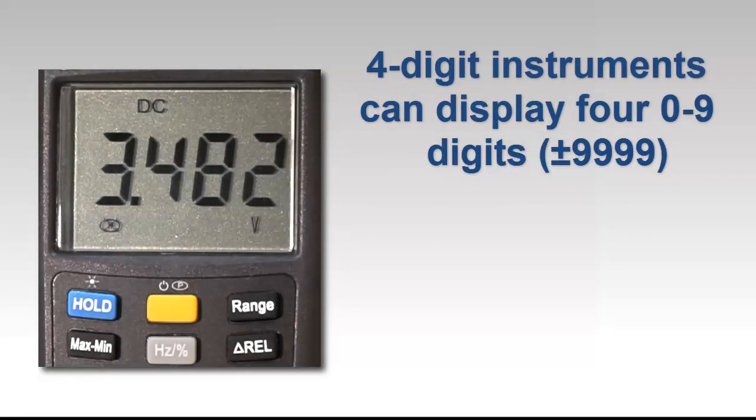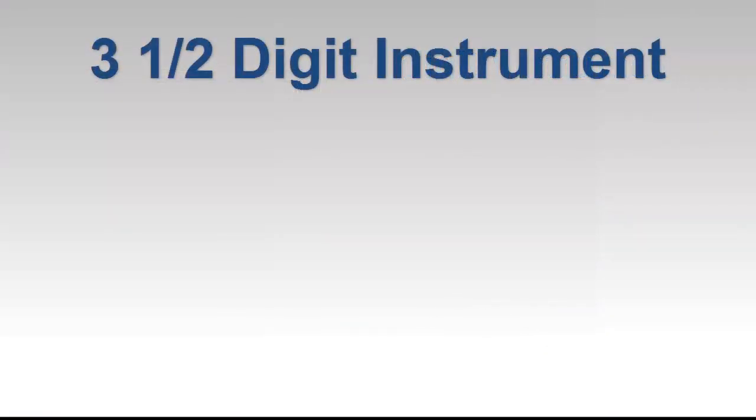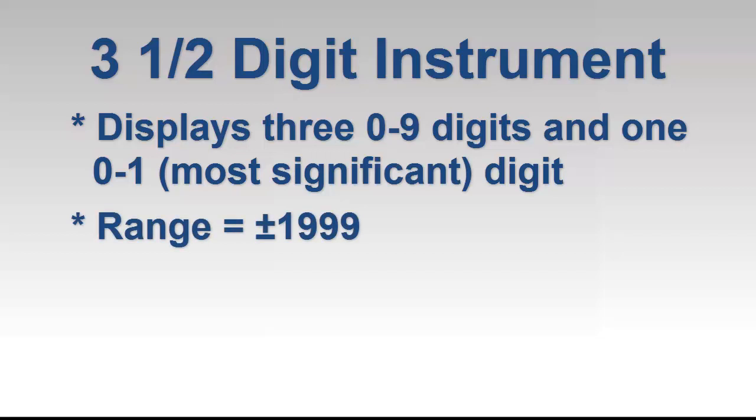Digits defines the number of digits an instrument can display. For example, a four-digit multimeter can display four zero through nine digits. This fairly simple concept becomes more complex when the leftmost digit, usually called the most significant digit, cannot display the full range of numbers. For example, a so-called three-and-a-half-digit instrument can display either a one or zero as the most significant digit. Thus, the highest reading this multimeter can display within a single measurement range is 1999. Readings greater than this must be displayed in a higher range, if available.